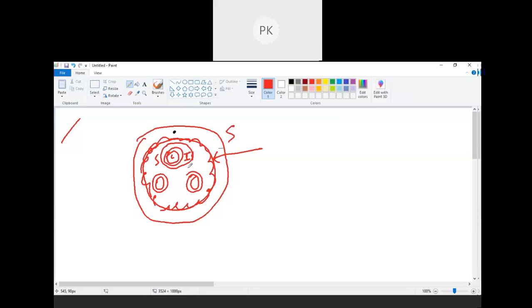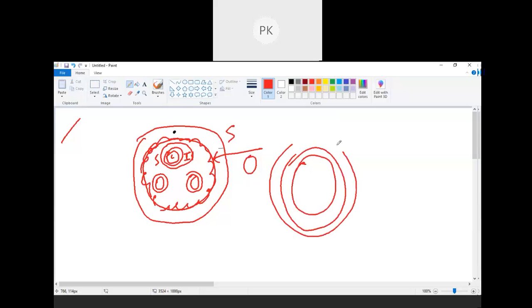electric field by all three phases, R, Y, B, because all three phases' field is subjected to it. So the net effect will be zero if it is a three phase cable. But if it is a single core cable, then what will happen? The armor will carry circulating current into earth at both sides.